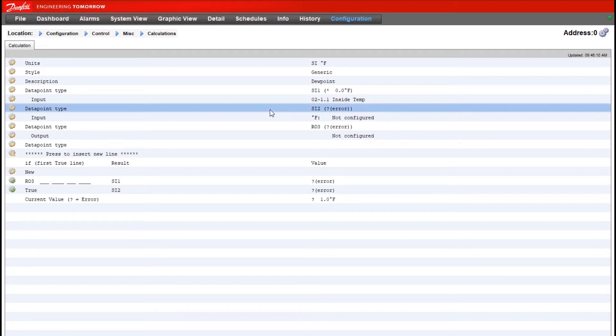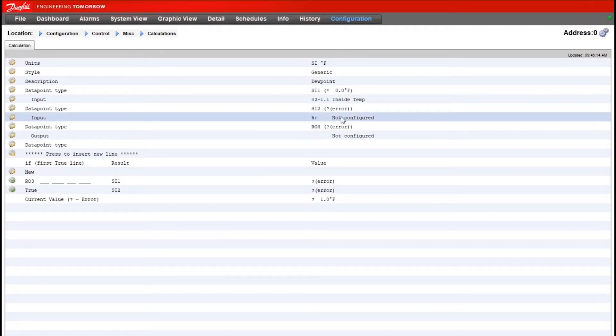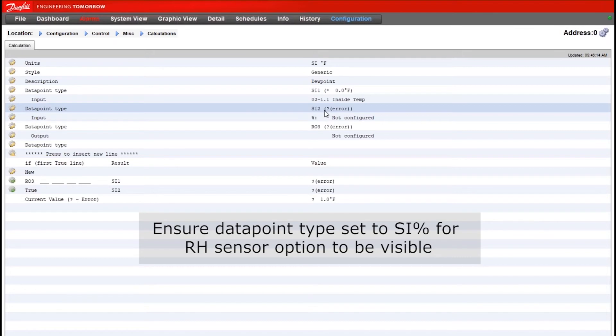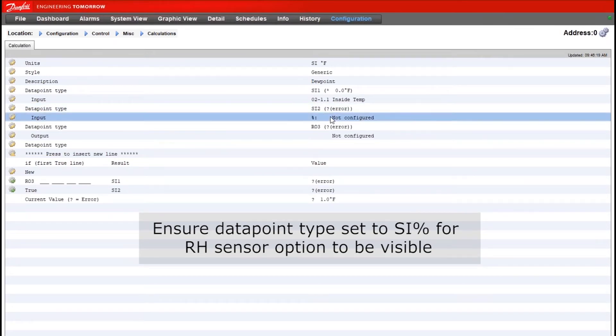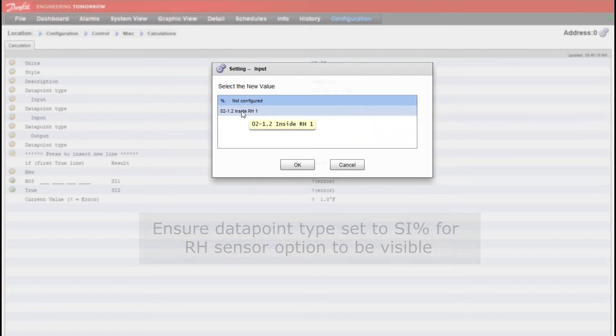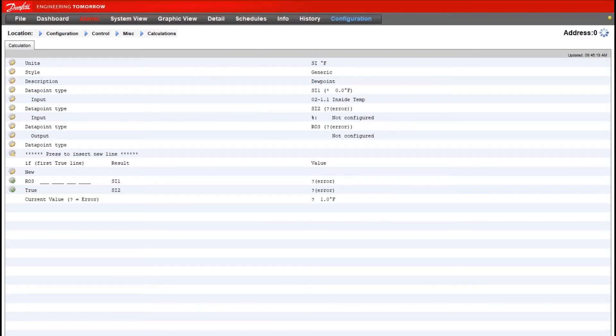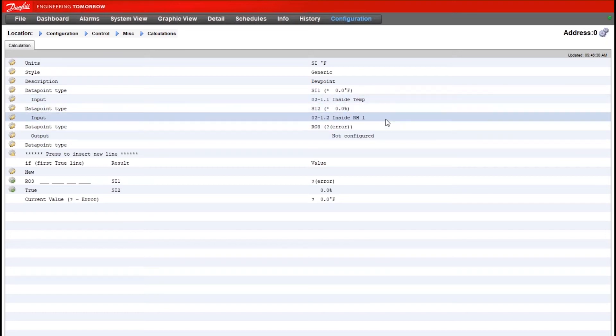Our second data point type—now we need to bring in our relative humidity value. So if we choose the data point type as a percentage, this will now give us any inputs that are based off of a percentage, like our relative humidity. So we'll be able to select that from the list here, and now we have our two sensors that we need to calculate dew point.